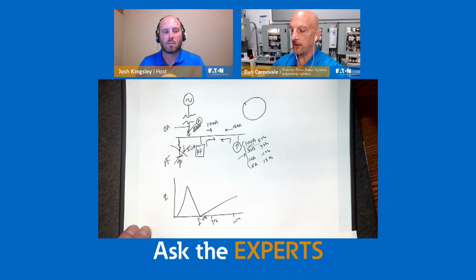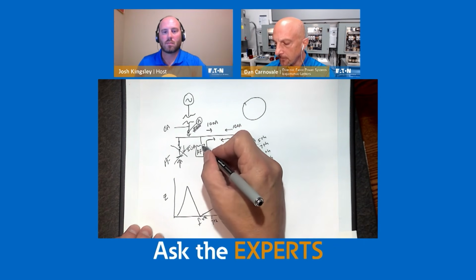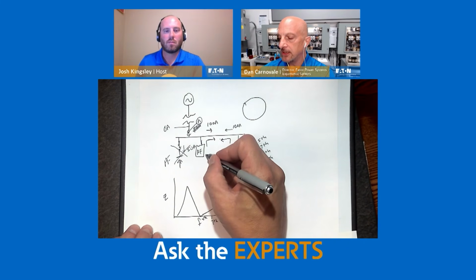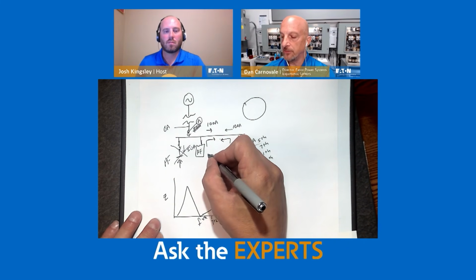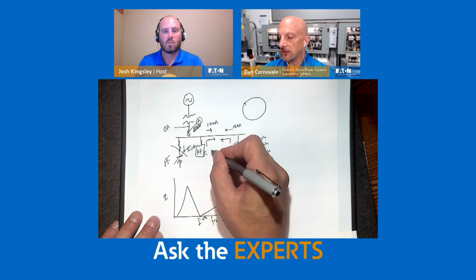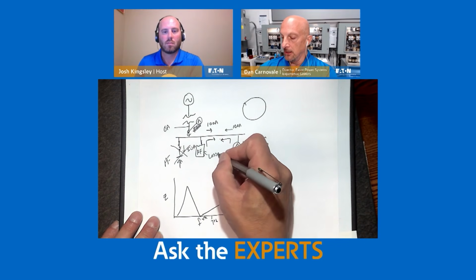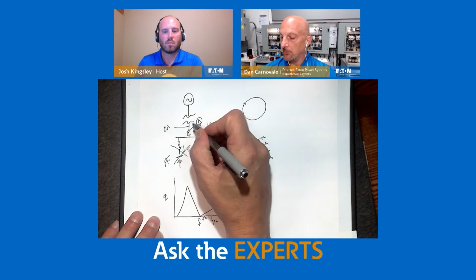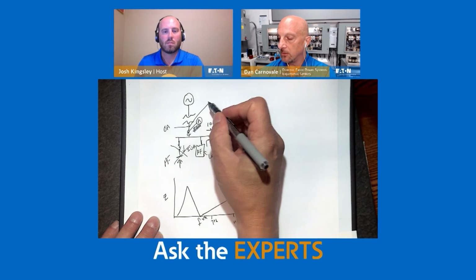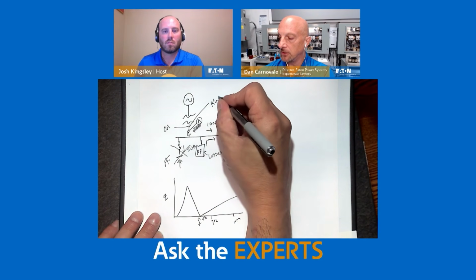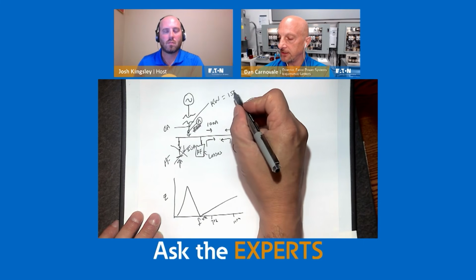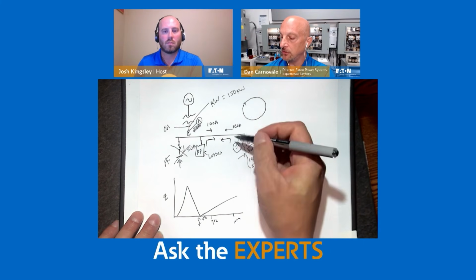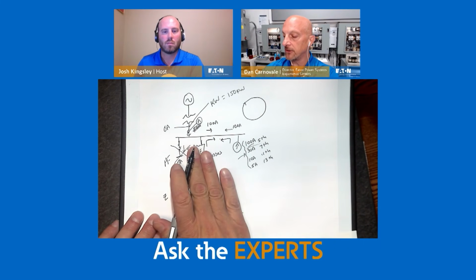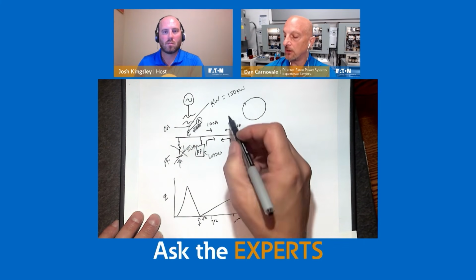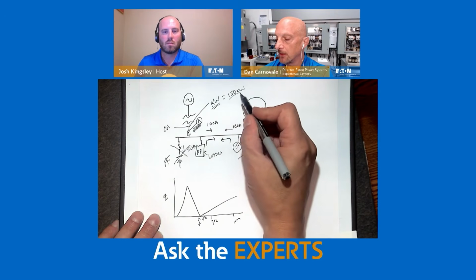But the other part of that, addressing losses: what does this thing do? It injects current, and the way it injects current is through a power converter, and this thing has losses. So let's say you measure not current up here, but power, kilowatts. And let's say your load was 150 kilowatts, and you have all your harmonic current on there. You turn off your active filter at 150 kilowatts, and then you turn on your active filter. Your kilowatts actually will go up a little bit.